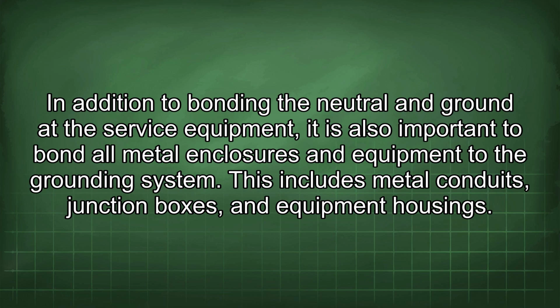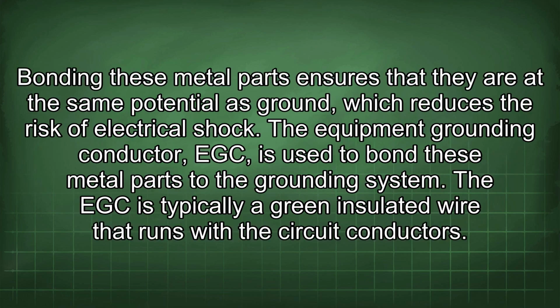In addition to bonding the neutral and ground at the service equipment, it is also important to bond all metal enclosures and equipment to the grounding system. This includes metal conduits, junction boxes, and equipment housings. Bonding these metal parts ensures that they are at the same potential as ground, which reduces the risk of electrical shock. The equipment grounding conductor (EGC) is used to bond these metal parts to the grounding system.